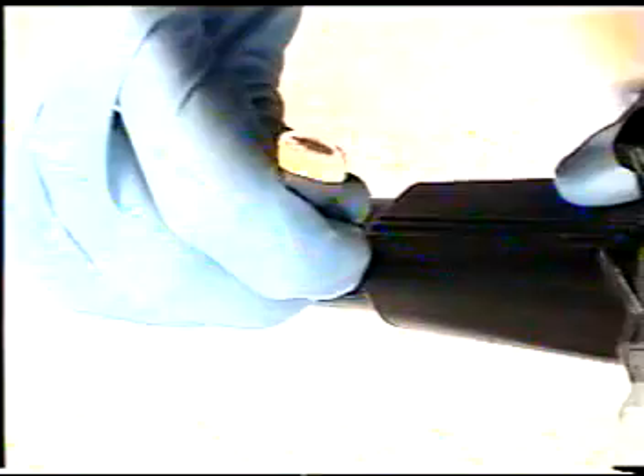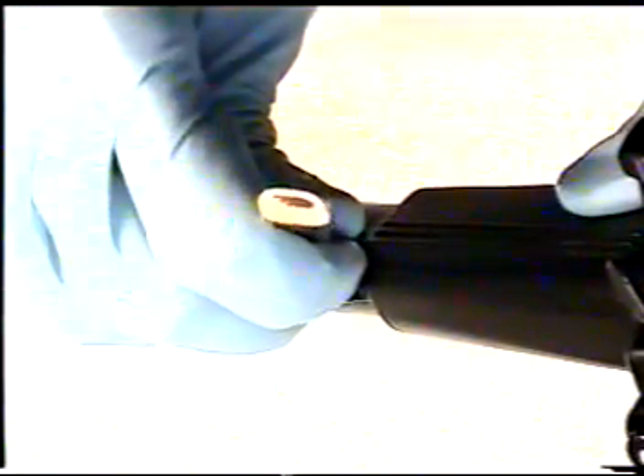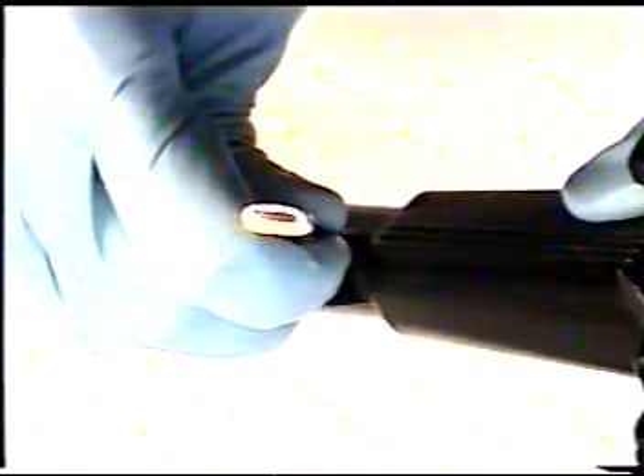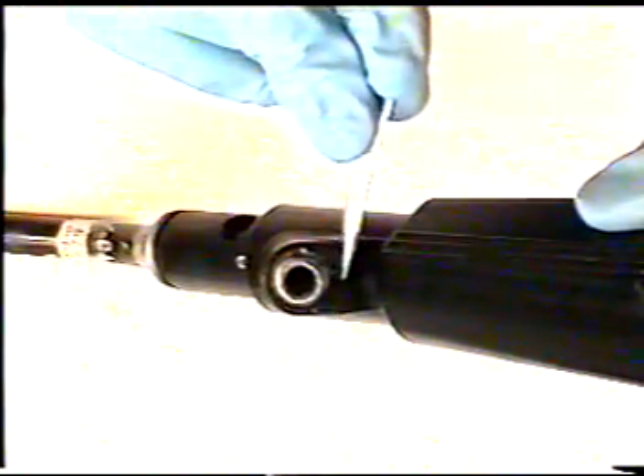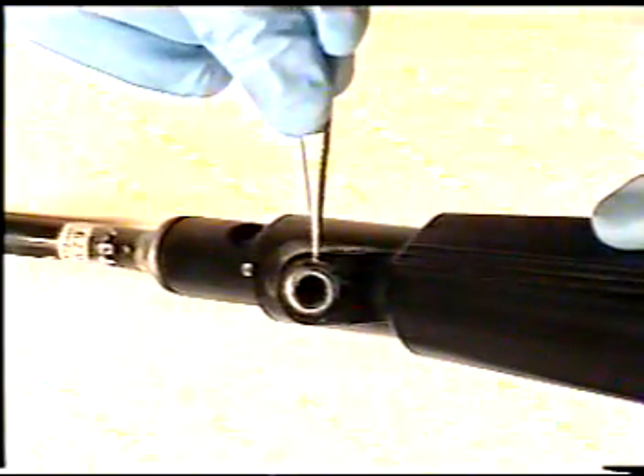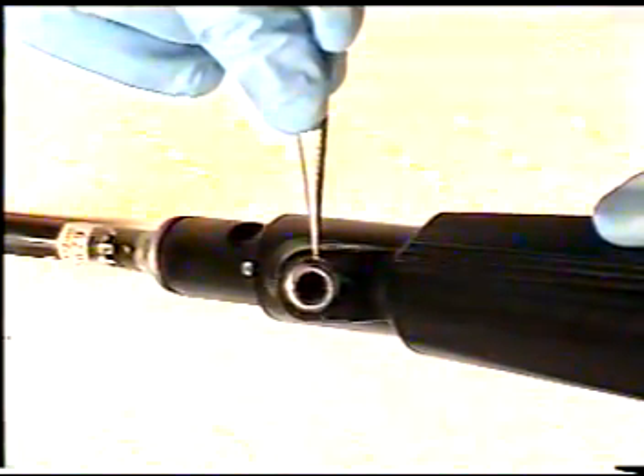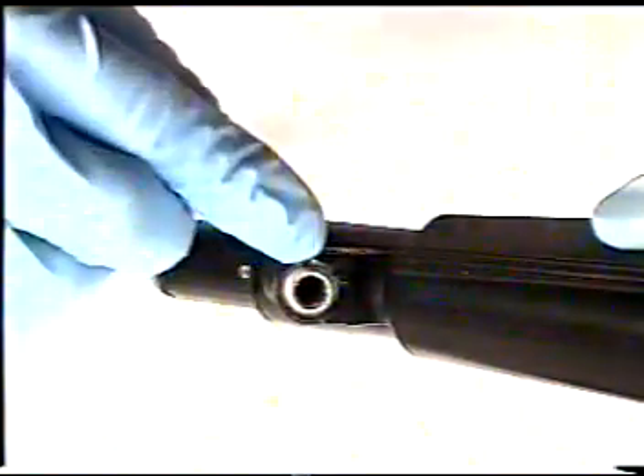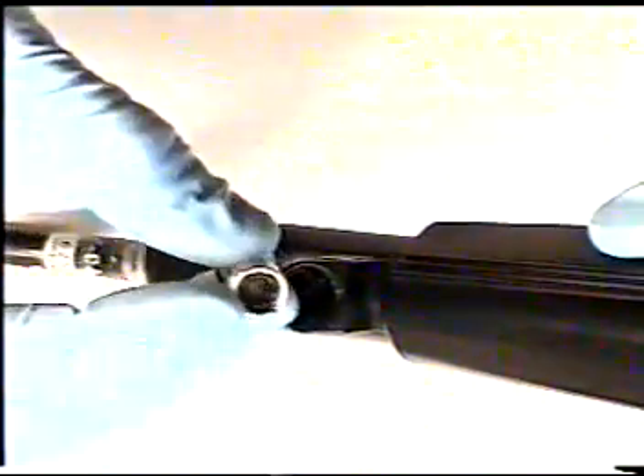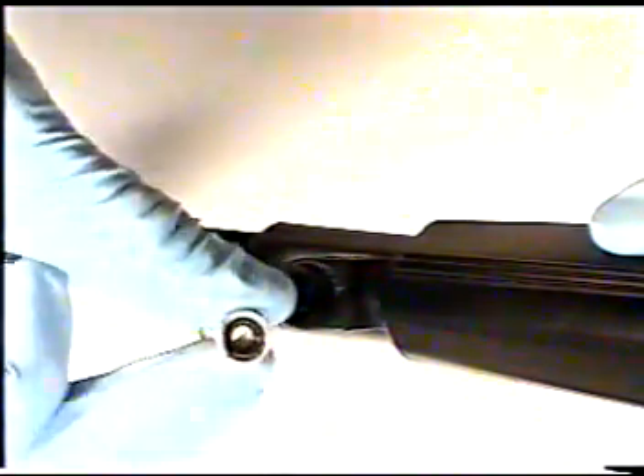Again, using your tweezers, turn the biopsy port itself counterclockwise 90 degrees. This moves the notch from where the key was to the 3 o'clock mark. Once it is at the 3 o'clock mark, we can pull out the biopsy port. The reason is that there are two notches, and once turned 90 degrees, this locks the biopsy port in place, making a seal with the O-ring.